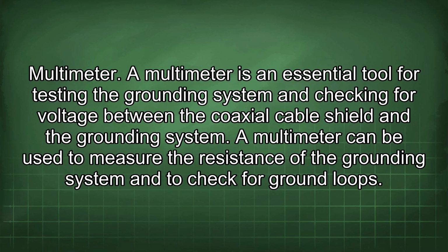Multimeter. A multimeter is an essential tool for testing the grounding system and checking for voltage between the coaxial cable shield and the grounding system. A multimeter can be used to measure the resistance of the grounding system and to check for ground loops.